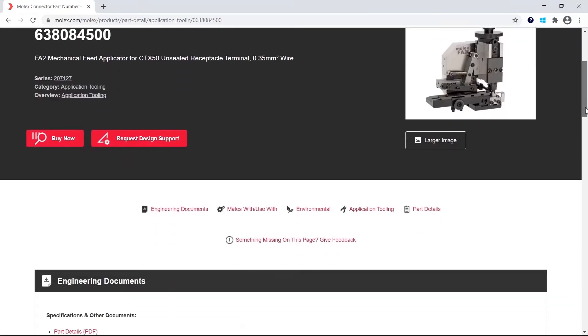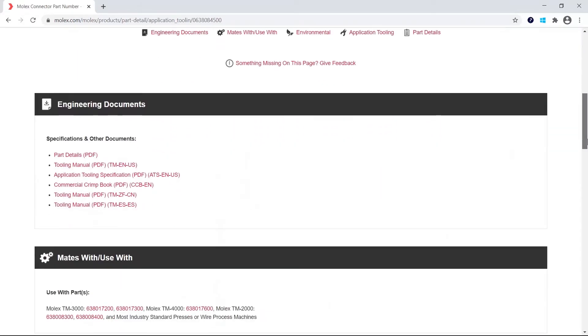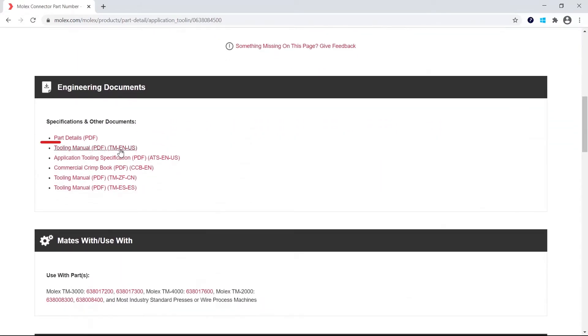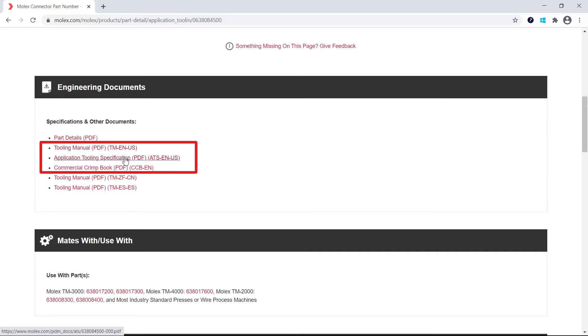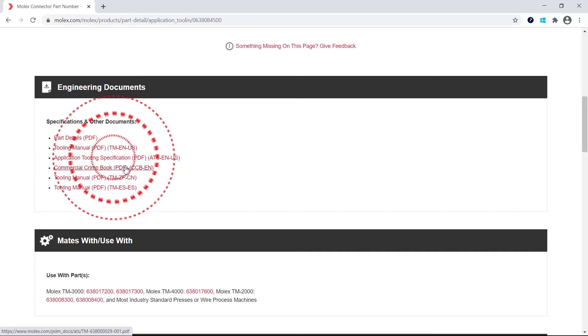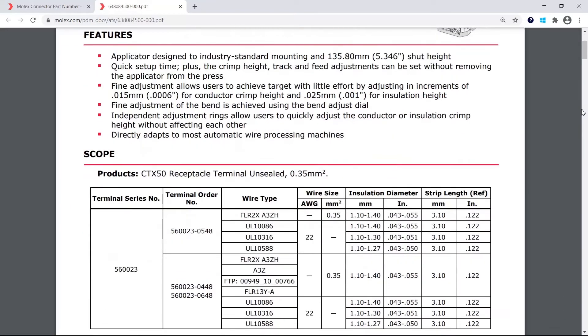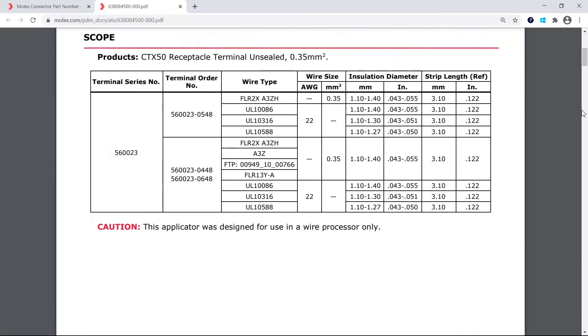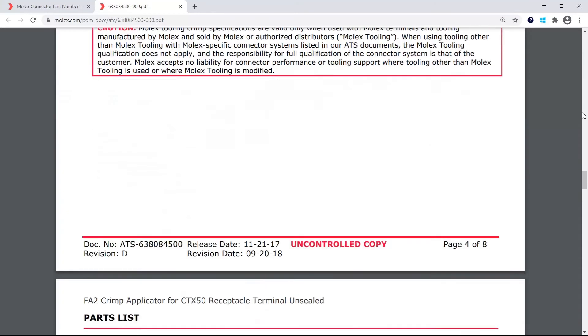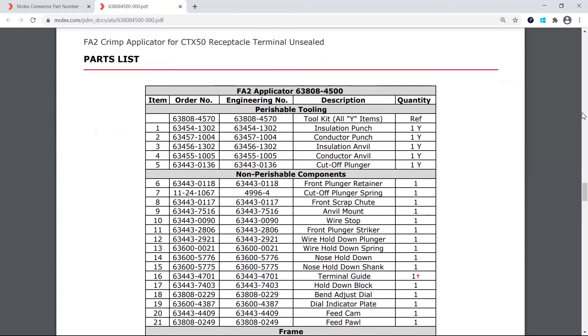From the tooling main page you will see application tooling specification, the commercial crimp book, and the tooling manual which are the main documents listed here. The application tooling specification provides all the details for that tool including the terminals that will crimp, the wire gauge range, insulation diameters, as well as other critical dimensions and specifications. This document also contains information for identifying replacement parts for tooling.